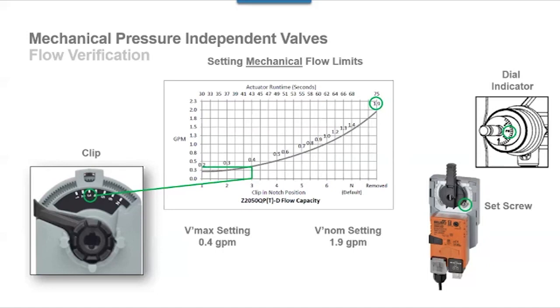One other thing I wanted to bring up, I get this question a lot. Well, what do I do if I'm flushing? Well, my advice to you is to verify with the manufacturer their requirement. We don't have a requirement to make any change in the valve when you do a flush. I know there are some companies that will say, okay, take the setting the valve is at and move it to this position for a flush, and then move it back to the set position. So that's something you need to look at with each manufacturer.